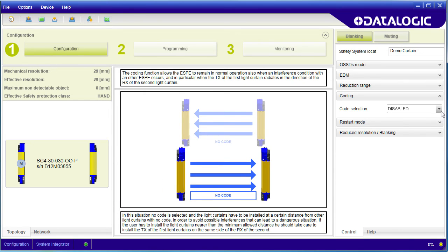The beams sent between the two units are digitally encoded, which gives you a super reliable performance. But if you have another set of light curtains nearby, they could interfere with each other if they transmit the same code. Now, normally you would set those curtains up like this, where one transmits from right to left and the other left to right, so there's no way they can interfere with each other. You can also reduce the possibility of interference by making sure the sensitivity of the light curtain pairs is reduced to the smallest you need back here in the previous step.